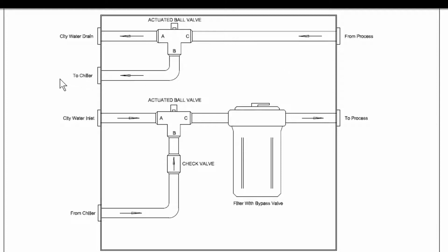Now, on the Legacy chillers, if you have any issue with respect to the chiller operation or the power gets turned off, whatever, the PLC will make the decision to de-energize the 2 actuators here, and that will force these 2 valves to connect between A and C. Okay, so we'll disconnect from B and C and we will connect to A and C. So A and C here, A and C here. So when we're in city water mode, we're coming through here. It cannot go this direction. It goes through your filter in this case. Remember I mentioned earlier though, if you don't have this filter, you need to filter it out here. And you go out to your process. You come from the process. Again, A and C are connected back to your drain line, and that goes out to your floor drain.